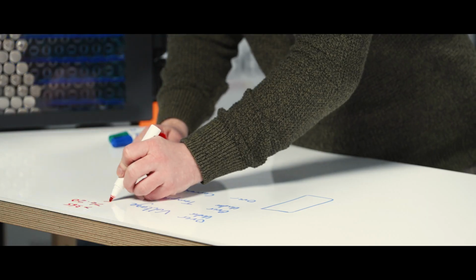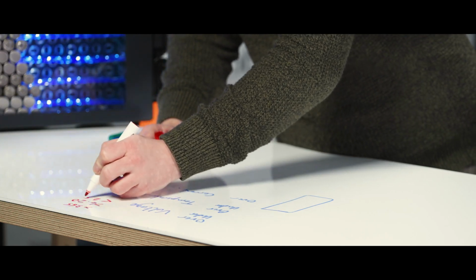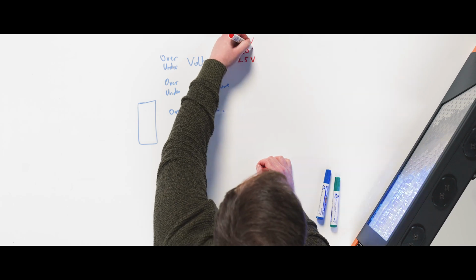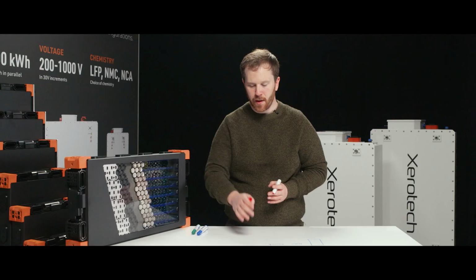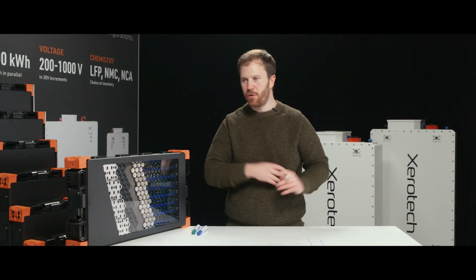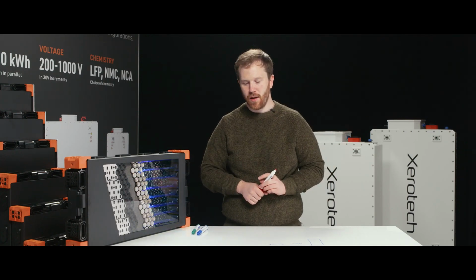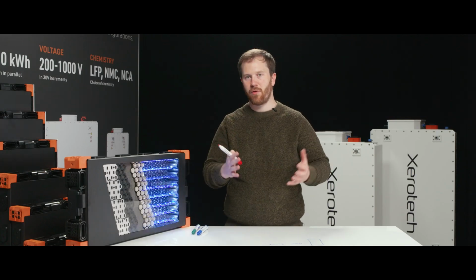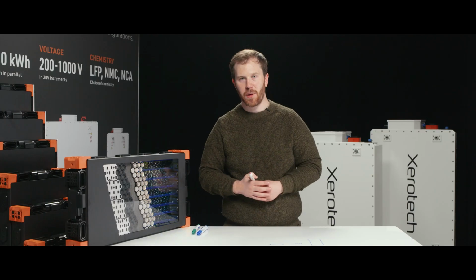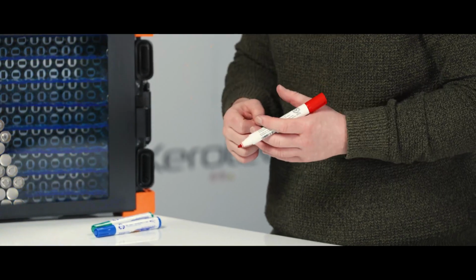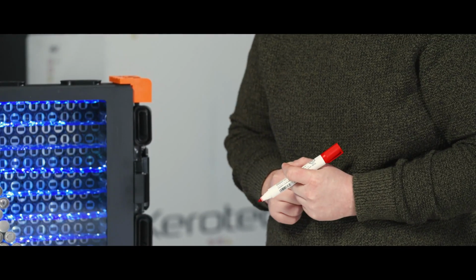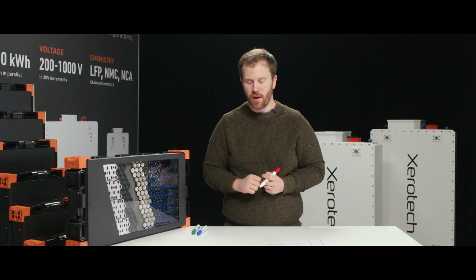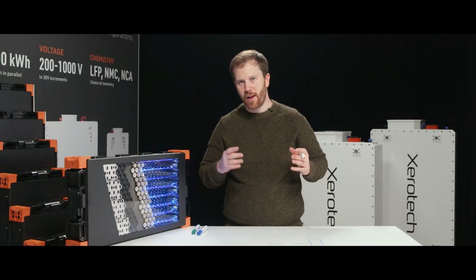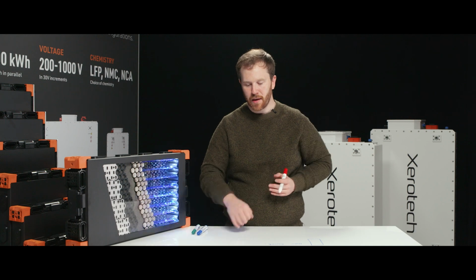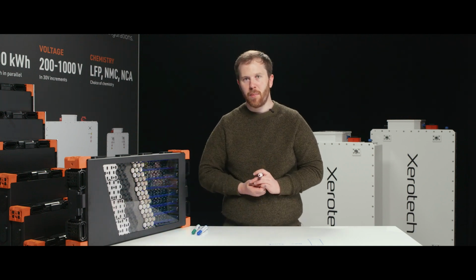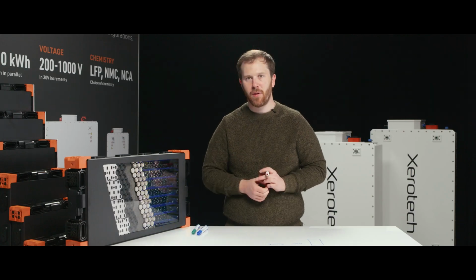And for most chemistries, when you go below 2.5 volts, also very bad. So with a battery cell, 0 volts is not zero. Something is totally wrong if you've managed to achieve 0 volts in a battery. The laws of physics between the different electrochemistry parts of a battery mean that 0 is actually 2.5 volts. So when the battery is actually reading 0 volts, that means it's under a small bit of load pulling it down below the 2.5 volts. But when you're below 2.5 volts, you're causing irreversible electrochemical damage to the battery cells. This won't result in a fire risk, but it will result in an irreversible capacity loss.